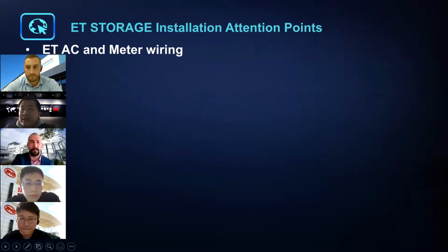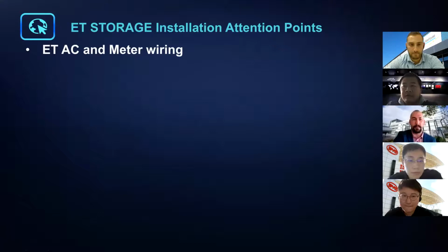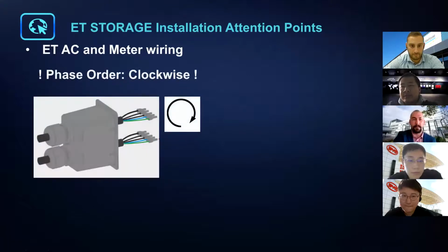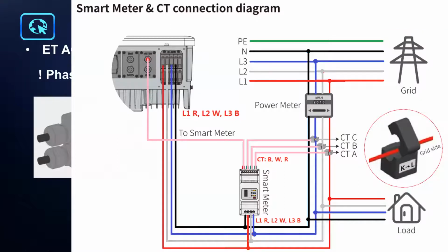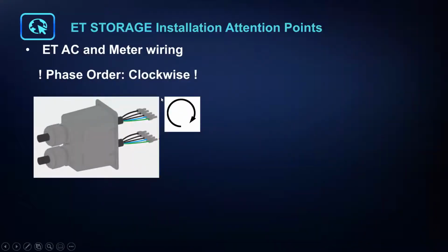This slide mainly talks about the AC wiring for our storage inverter. There are 2 points to be careful about. The first is the phase order, because the three-phase hybrid inverter backs up the three-phase load, and a three-phase load has a phase order. For GoodWe inverters, the phase order is clockwise. So when you finish the wiring, always make sure your phase order is clockwise. If it's not clockwise, the inverter will show a phase order fault on the app, and also on the inverter itself.